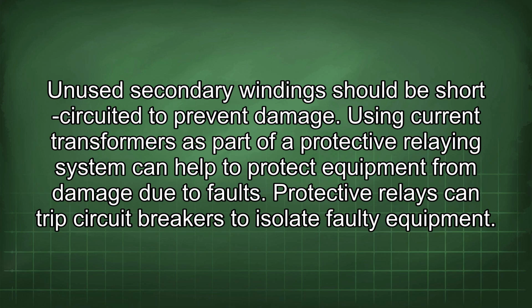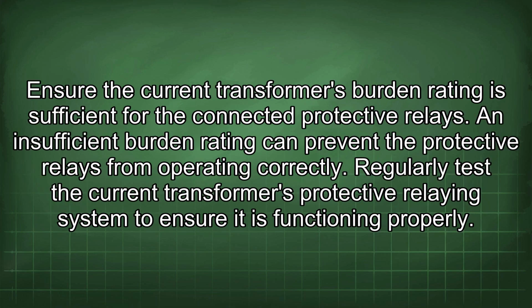Using current transformers as part of a protective relaying system can help to protect equipment from damage due to faults. Protective relays can trip circuit breakers to isolate faulty equipment. Ensure the current transformer's burden rating is sufficient for the connected protective relays. An insufficient burden rating can prevent the protective relays from operating correctly.